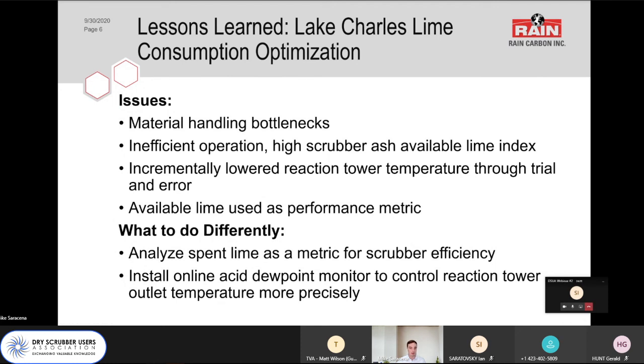What would we do differently? Certainly continue to analyze spent lime as a metric for scrubber efficiency immediately upon commissioning. It took us a few years to understand the nature of that reading and how important it could be. I think if we had done that from day one, we would have had much better information and continue to do it. We also, at a certain point, thought the scrubbers were as good as they were going to get. We stopped taking the samples, and we don't have as thorough historical data as a process engineer like me would like to see. As I mentioned in the last slide, I feel like I'm plugging for these online acid dew point monitors, but I really think that, if there was one thing about our systems that I wish I had, it would certainly be an online acid dew point monitor. This would help with both corrosion and lime consumption optimization. Really, really an important metric to be able to have.